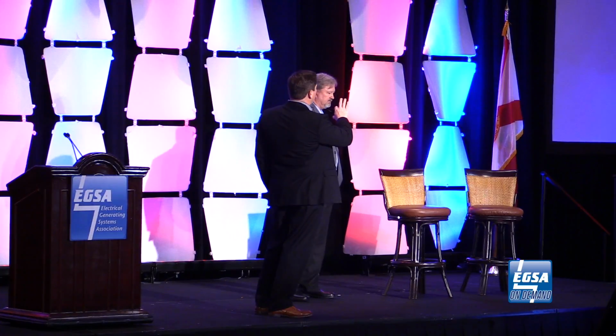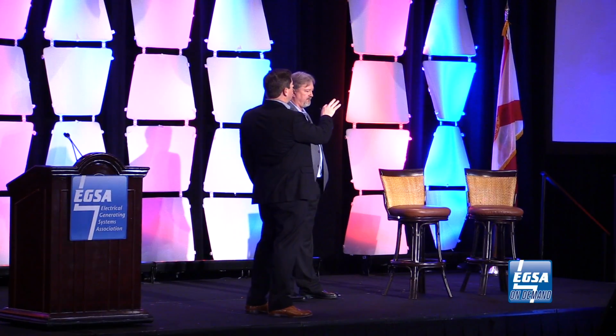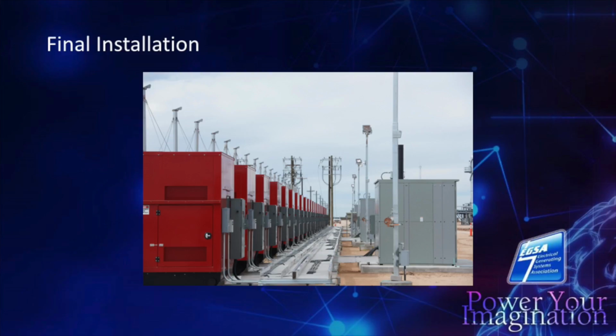Let me see if I have a picture of that. As far as the 23 units and the 5 group breaker controllers, those were all copper Ethernet into an industrial Cisco network switch that converted it to fiber, and we went underground fiber into the MCC building. From there, everything was fiber - the only copper we had was out at the site. I think after 300 feet you need to go fiber, so we ended up doing that there, which is nice functionality to be able to go back and forth with these controllers.